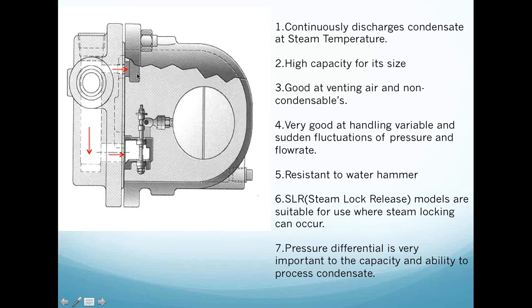Inside the actual body itself is a thermostat. That's why they call it a floating thermostatic steam trap. That thermostat is sitting there as a sentinel. When this trap is in a cold state and there may be air present, this thermostat will be open and it will process air and non-condensables. So that is a really big benefit to a float thermostatic steam trap, in that it really is good, and you do not need an external air vent if you use this particular type of trap.